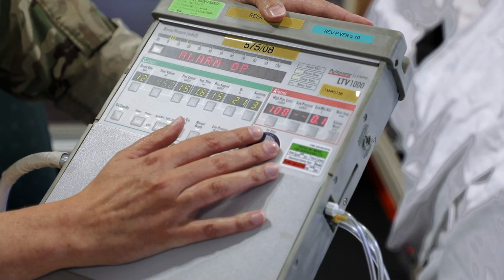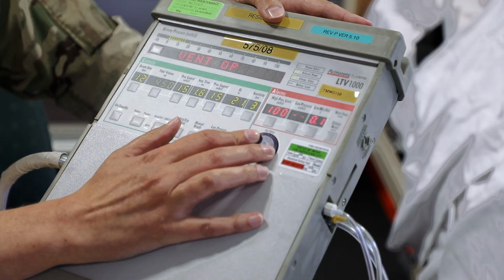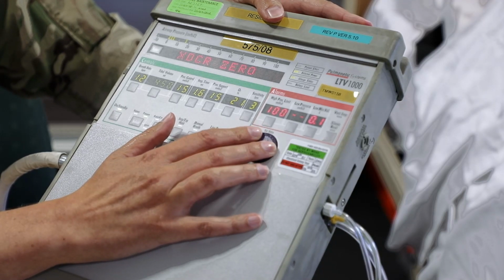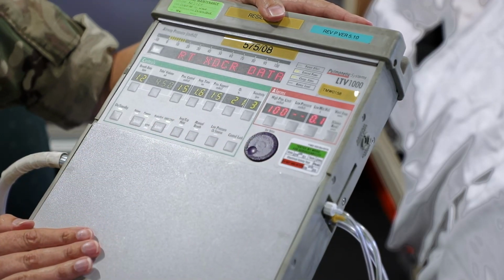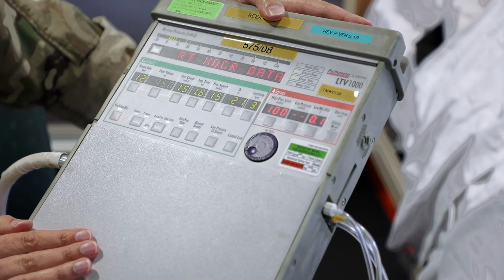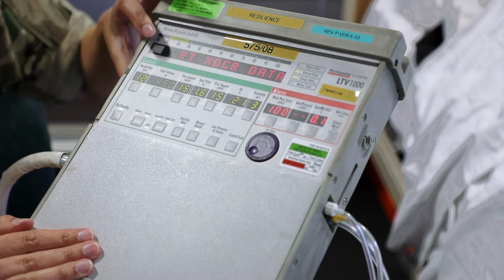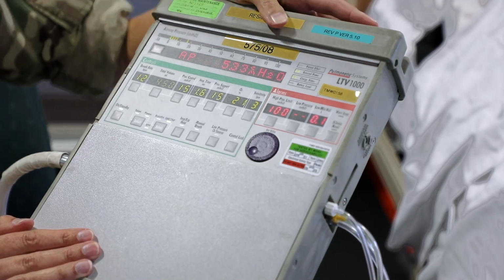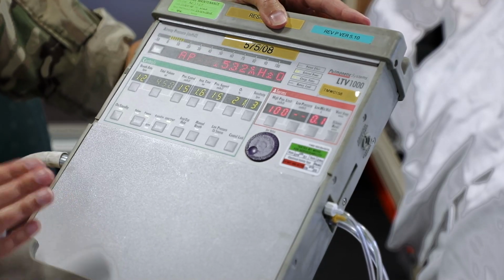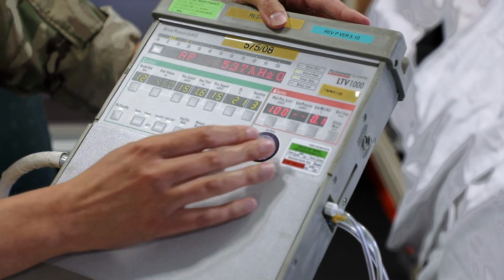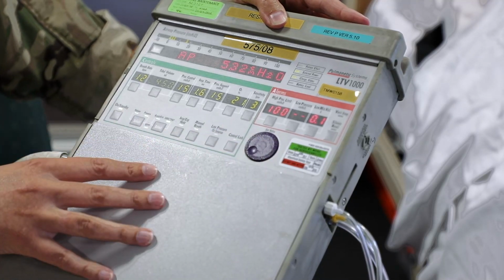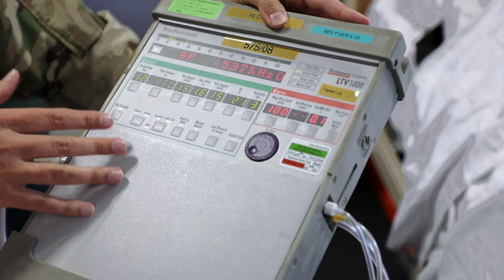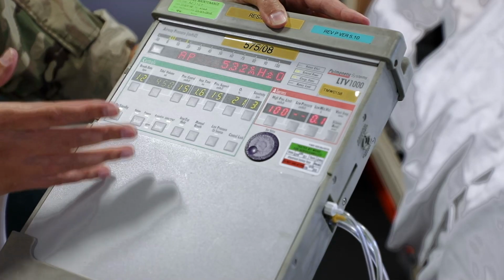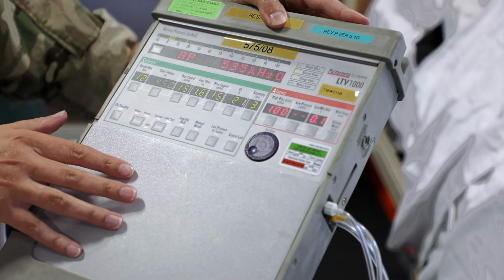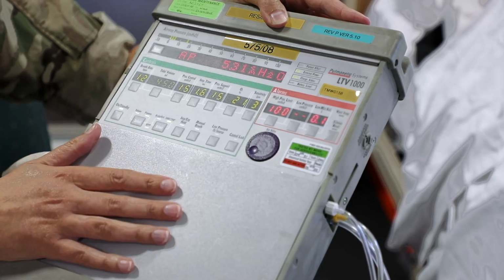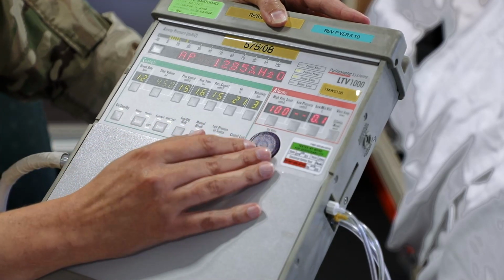So we've already been through some of these menus, but we'll just scroll through to the right until we get to where we want to be. And this is the menu you're looking for, this RT XDCR data. So this is the real-time transducer data. We'll press select, and it takes us into some numbers that it's monitoring as the LTV ventilates. We're going to do this as part of the pre-user check, but you can also do this during the mission. So say it's alarming at you for low oxygen or low battery voltage, you can go into the real-time transducer data to see this as well.